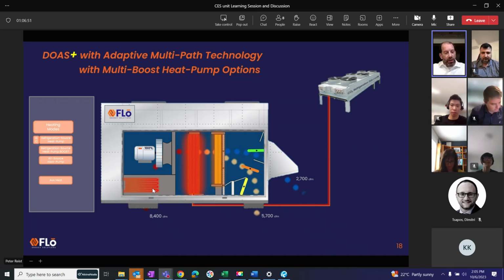We have the options. If it's a horizontal unit, then you put a duct heater on, you just buy one. In our case, if it's an internal unit, which is pretty common, we don't do natural gas integrated because it's not approved for venting into an internal, inside atmosphere. So then you need to use a gas duct heater approved for that purpose. Just keep those things in mind. That makes life easier. So it could either be an electric duct heater, or internal to our unit but then you have a vertical discharge - you just have to keep that in mind. We'll help you through all those details. So those are heating modes.